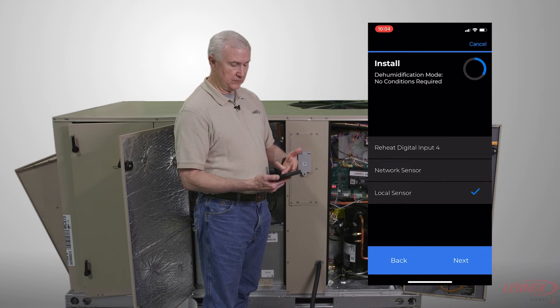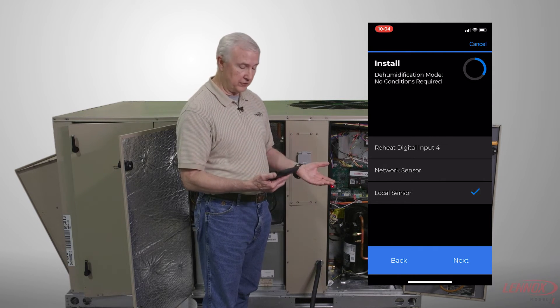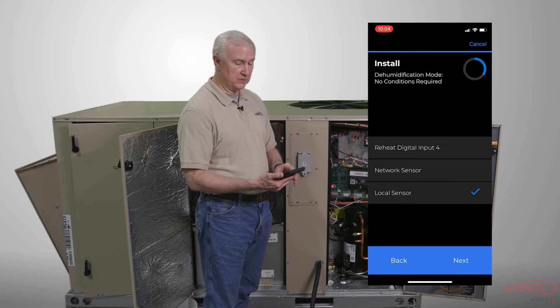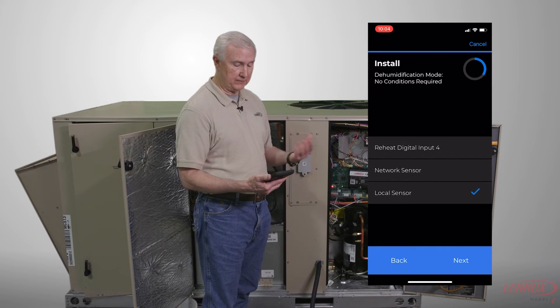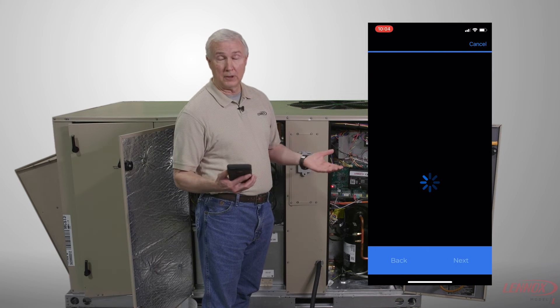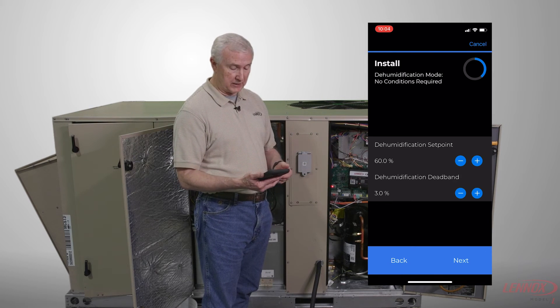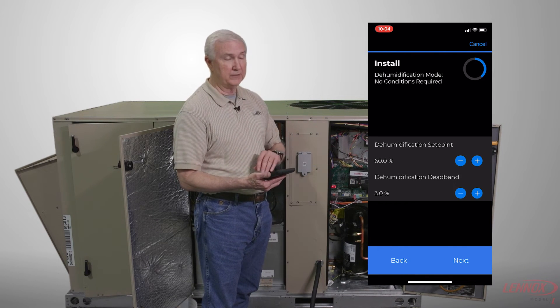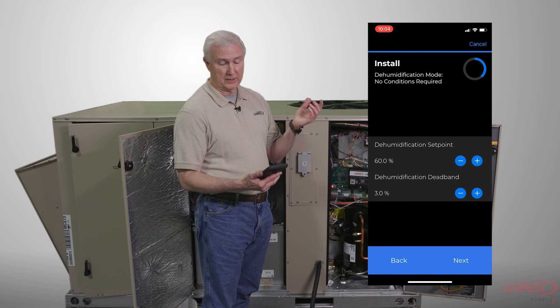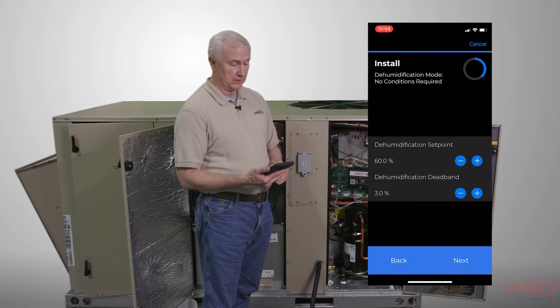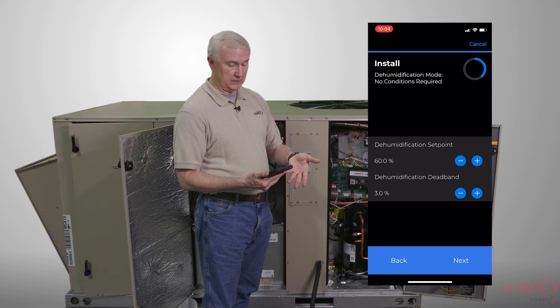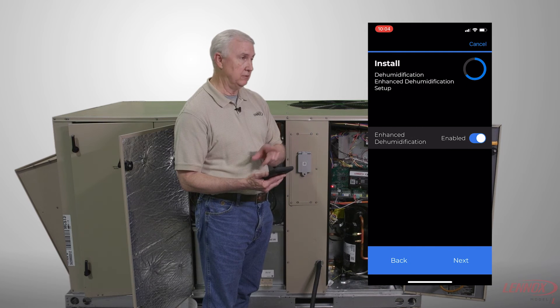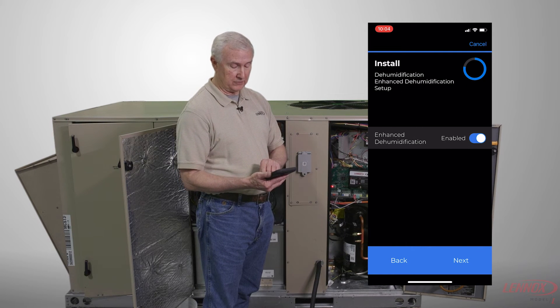Then you choose your sensor input for your dehumidification mode, whether it's going to be a local sensor, a network sensor, or a digital input. When you've selected that, hit next and move on where you will also choose your dehumidification set point and the dehumidification deadband. After those are selected, we'll move to the enhanced dehumidification menu to select or deactivate that.